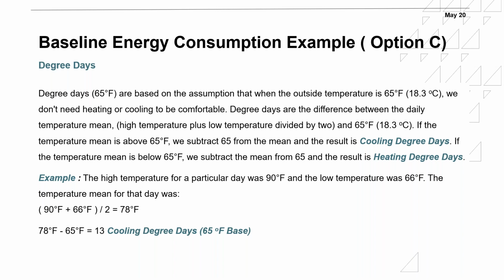As an example, let's say the high temperature for a particular day was 90 degrees Fahrenheit, and the low temperature was 66 degrees Fahrenheit. The mean temperature for that day would be 90, the highest temperature of the day, plus the low temperature, 66, divided by 2, which gives us 78 degrees Fahrenheit. So for that particular day, the cooling degree days is equal to 78 minus 65, which is the base temperature, equal to 13 cooling degree days. So for that particular day, we have 13 degree days. So we need to count.